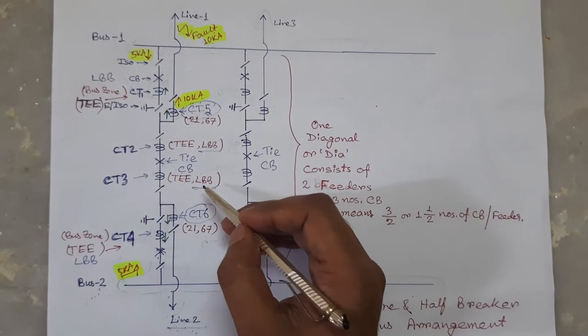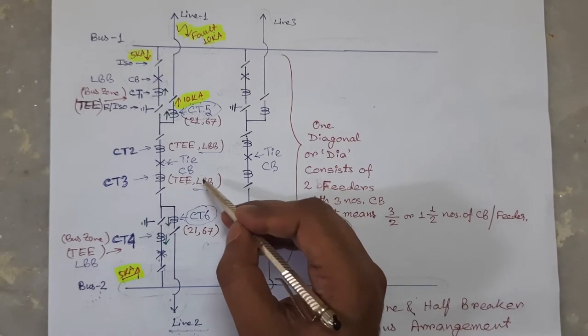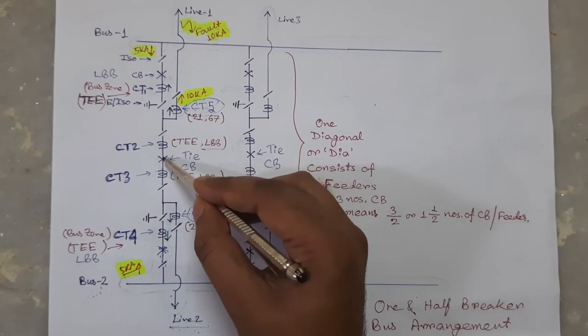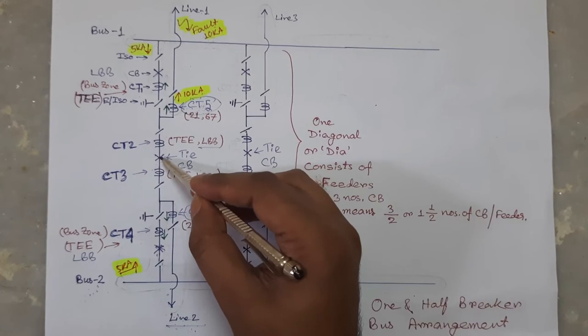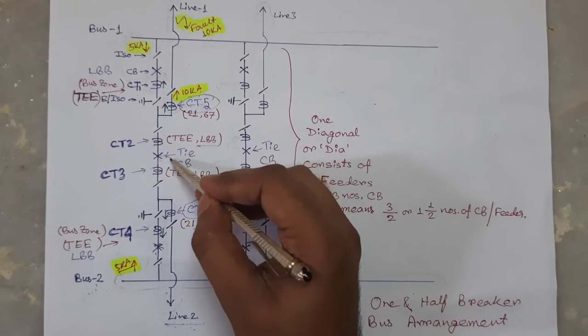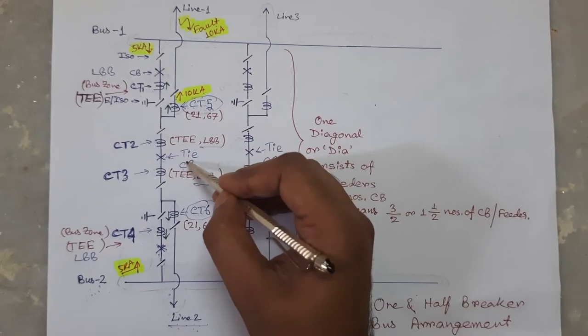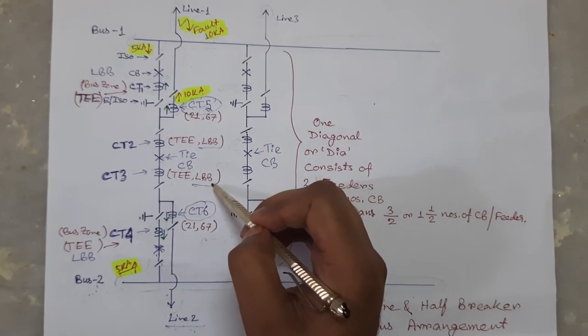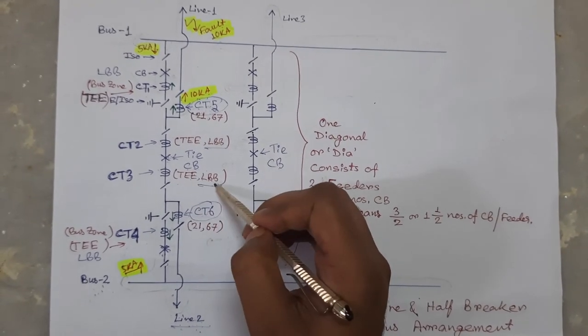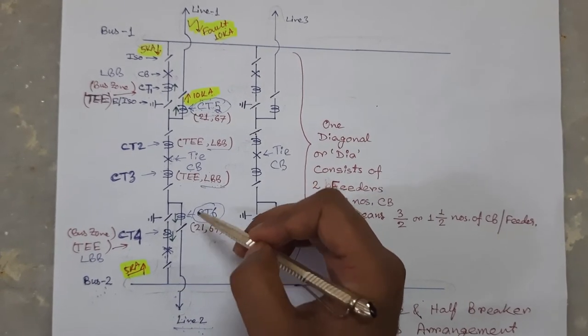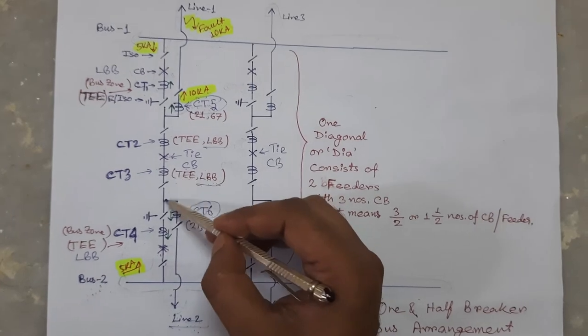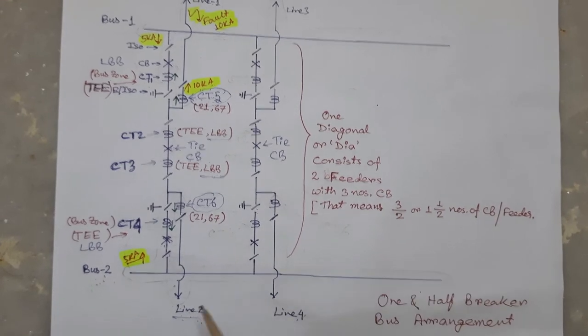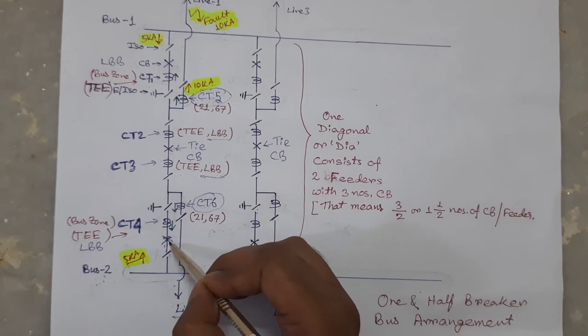after waiting the predefined time delay of 200 millisecond, tie LBB protection understands that this circuit breaker is not clearing the fault or this tie circuit breaker is unable to clear the fault. In that case, to clear the fault immediately, this tie LBB protection will operate and send trip command to this circuit breaker and also send a direct trip pulse to remote end of this line such that this line and this circuit breaker becomes dead.